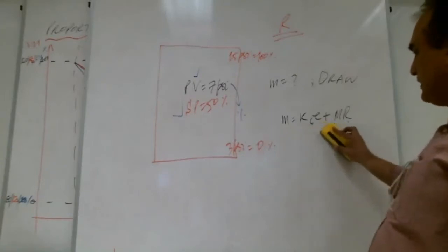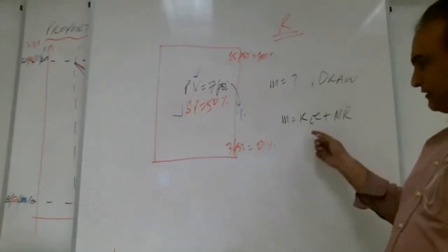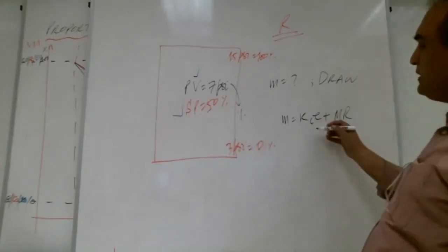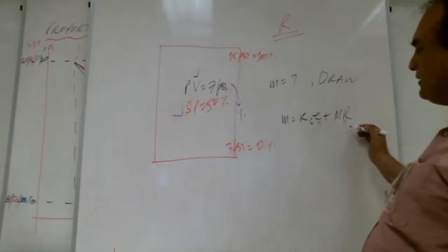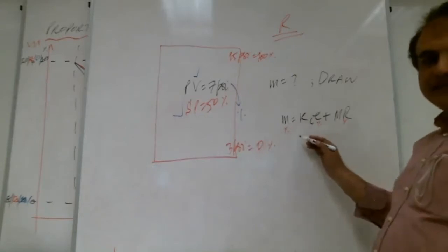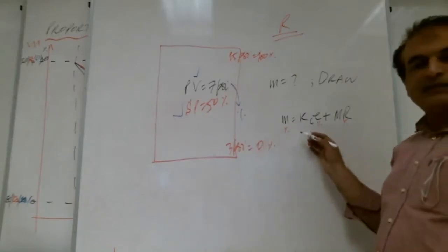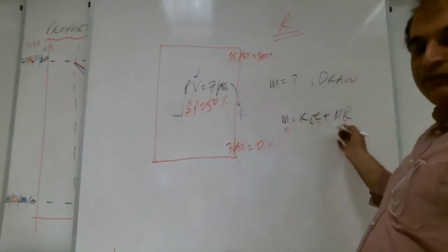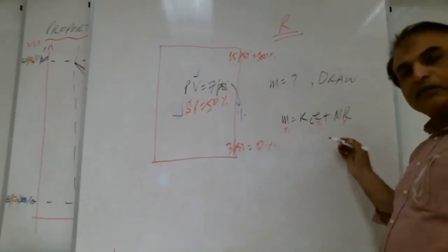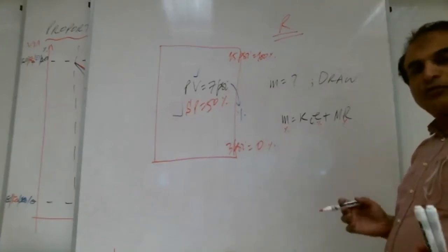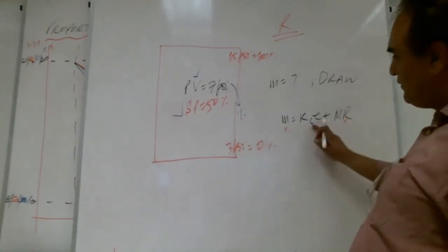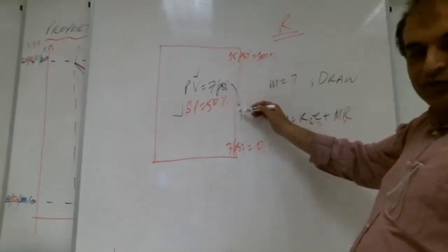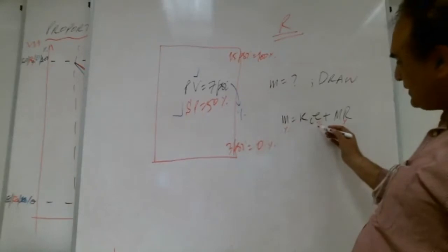See, Shabab, this formula works only in percentage. Error should be in percentage, MR should be in percentage, and output is also in percentage. This formula is just for percentage. If you want, you can convert into PSI or into milliampere, but how many units will you convert? So my suggestion is to always keep everything in percentage. This is the reason we need to convert the 7 psi into percentage, to get the error in percentage.